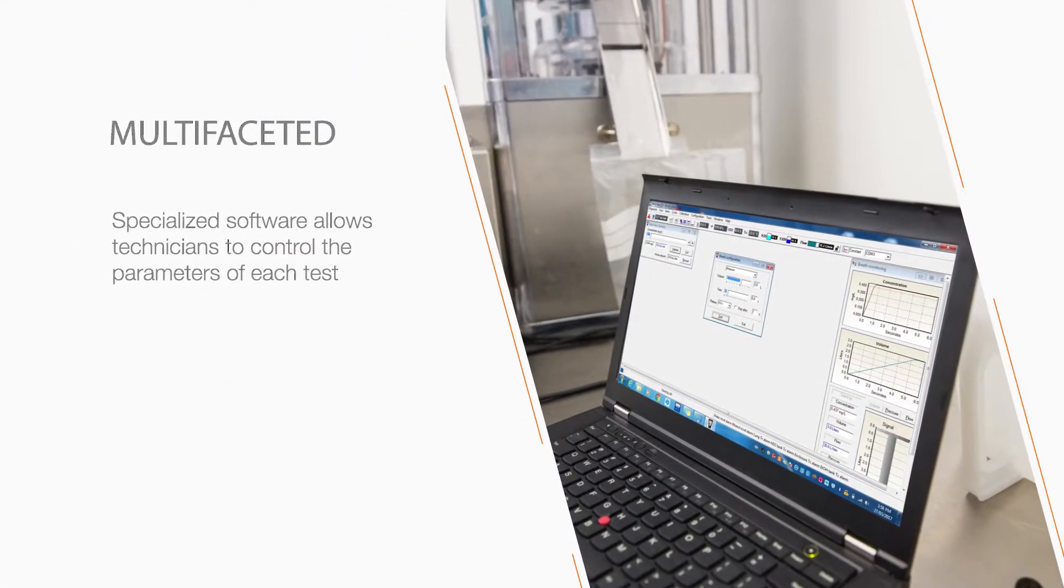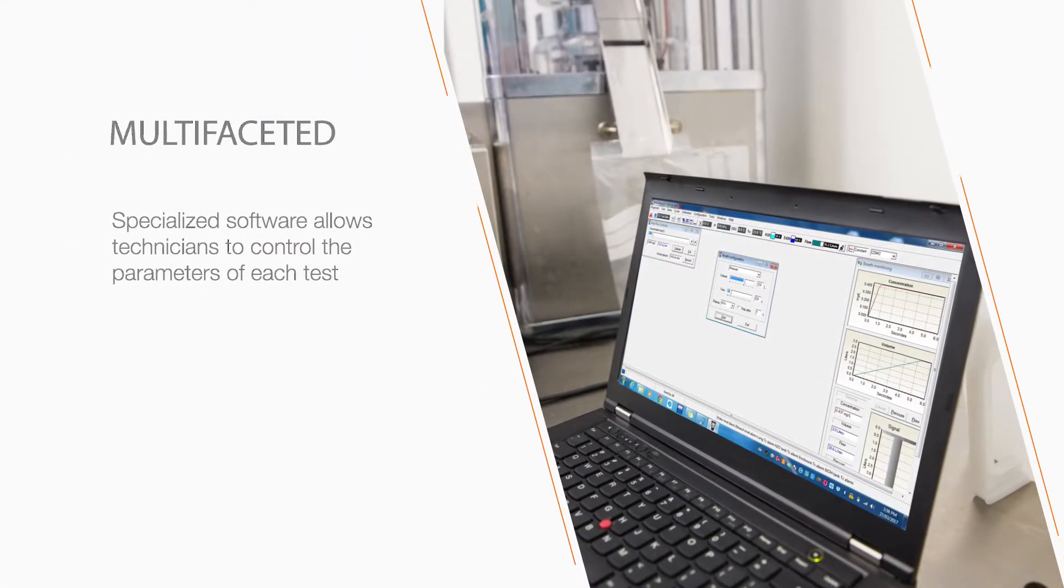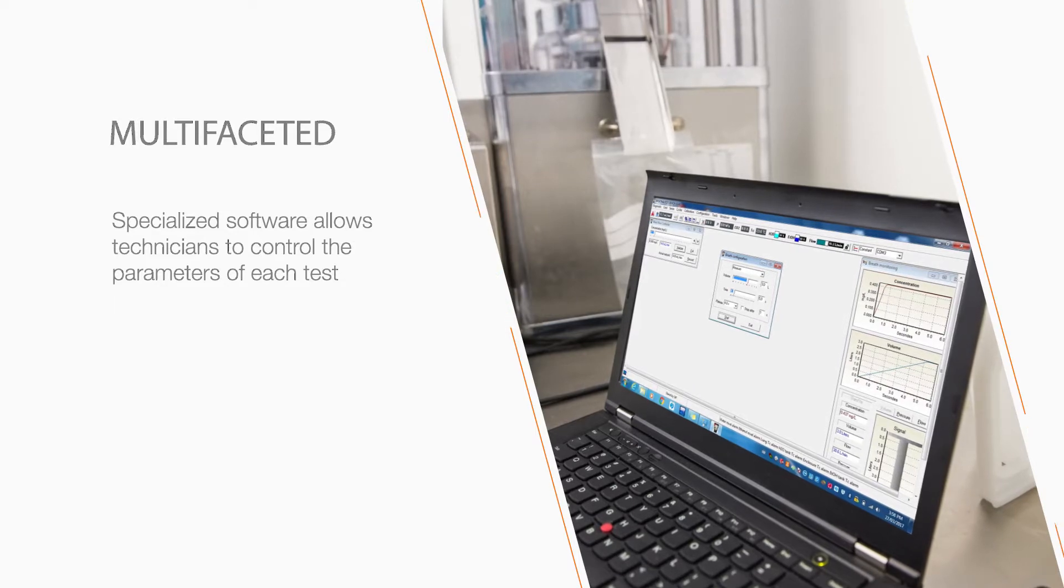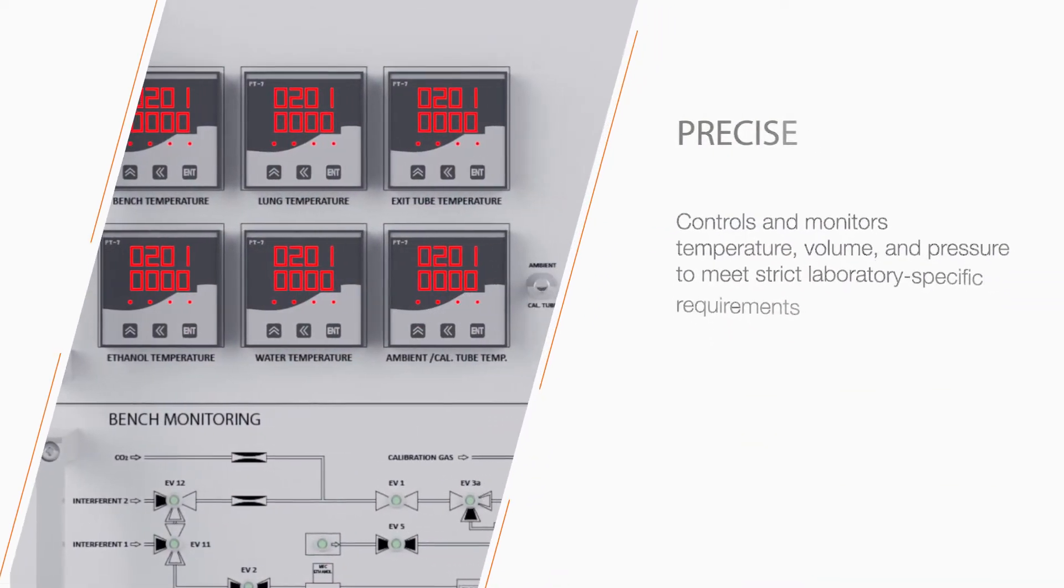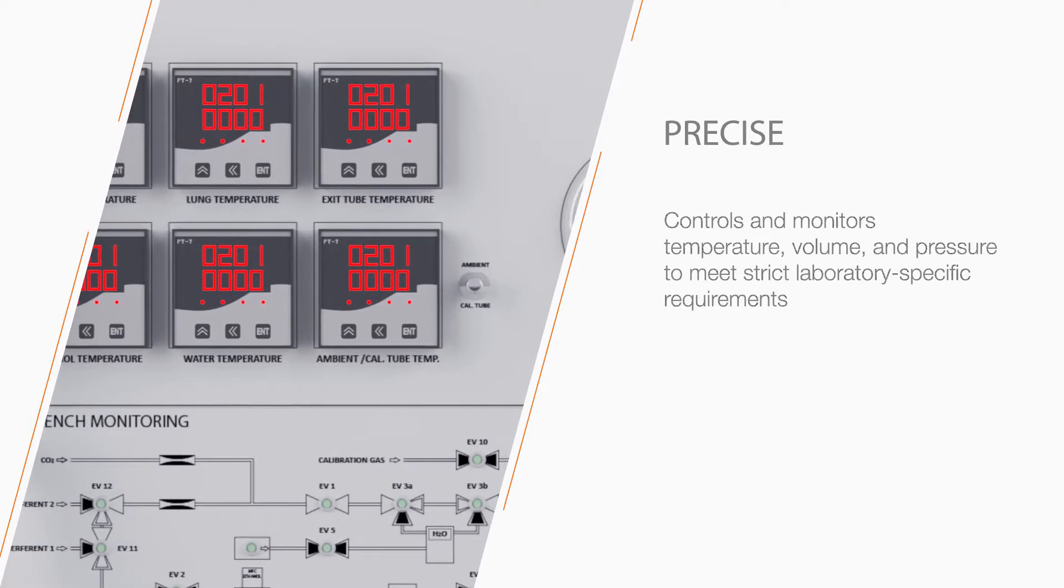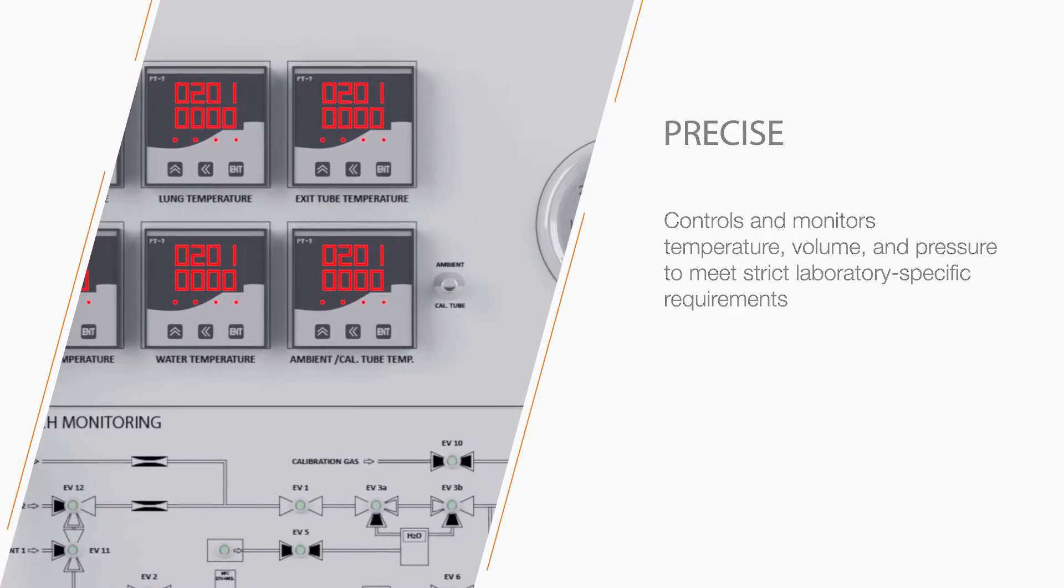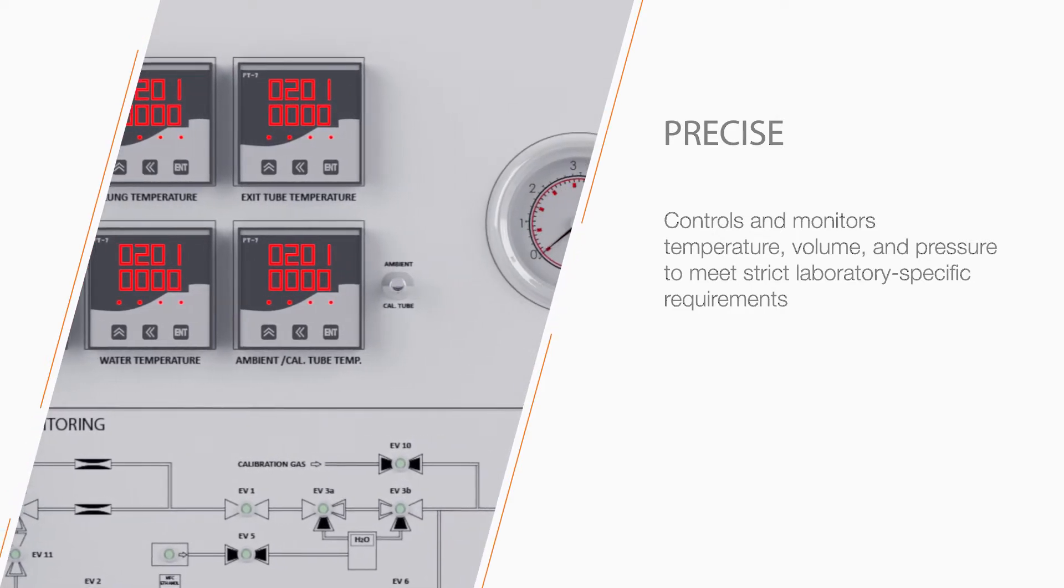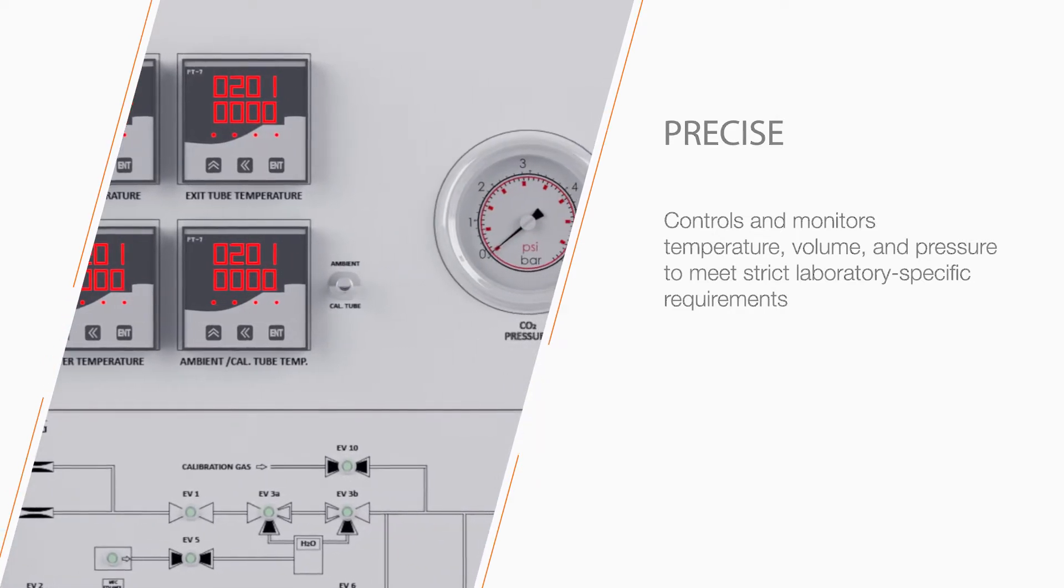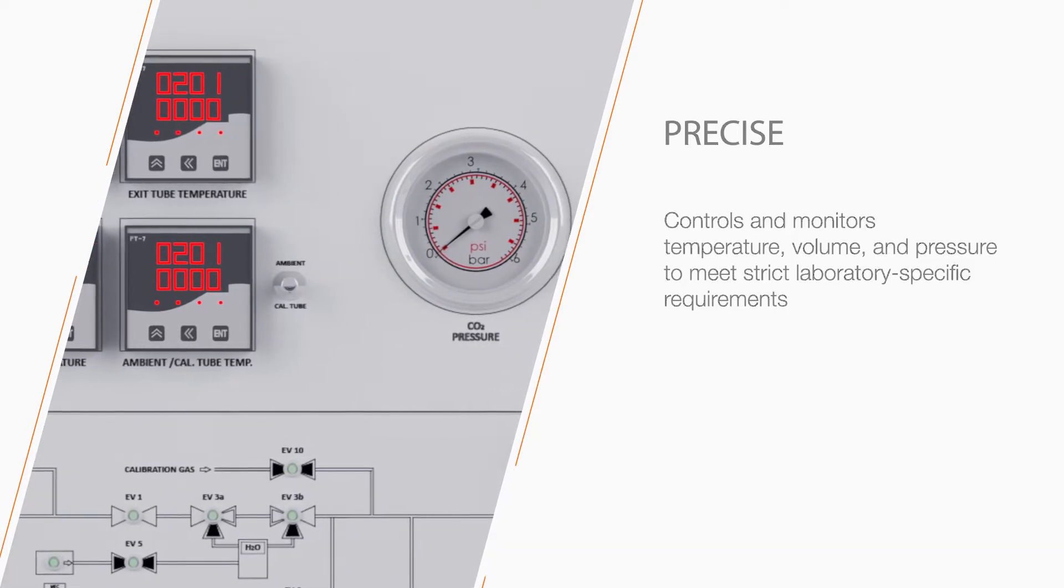Specialized software allows technicians to control the parameters of each test. This ensures that the composition, temperature, volume, and pressure of the simulated breath samples meets strict laboratory-specific requirements.